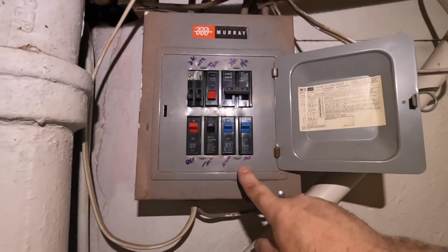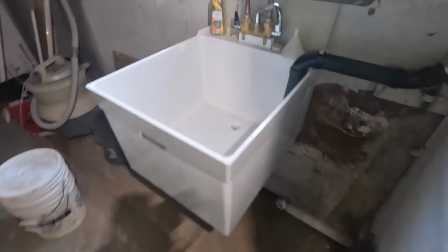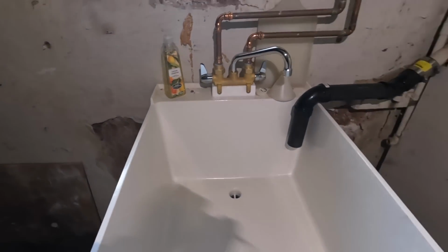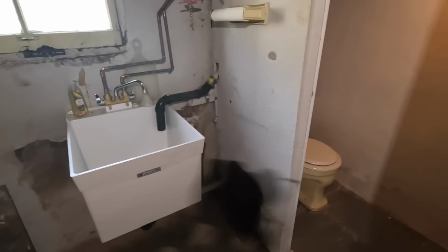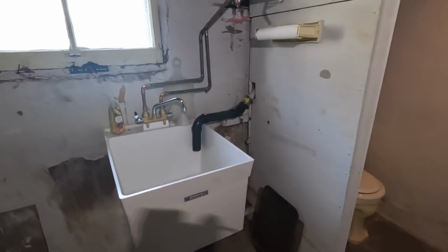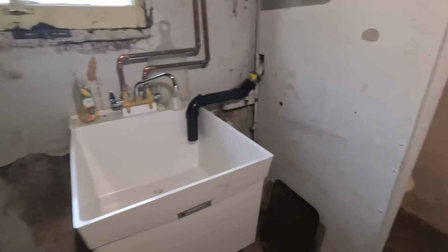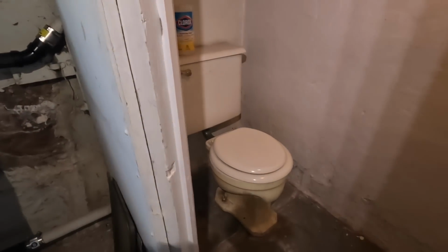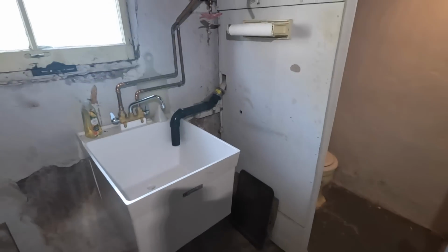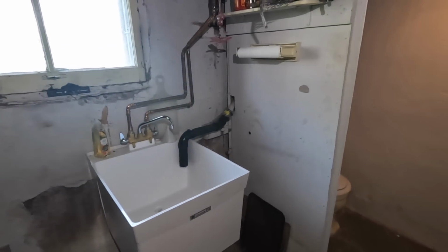So instead of opening everything up, we're just going to extend these circuits and obviously get this out of the bathroom. And it's a bathroom because there's a sink nearby in the area. The code specifically says the area which makes up the bathroom, a sink, and either a toilet or a shower, which we have. So this area, we could definitely say, is a bathroom.